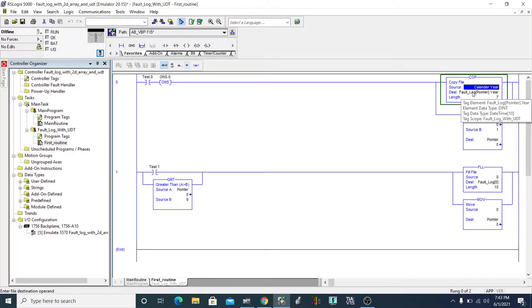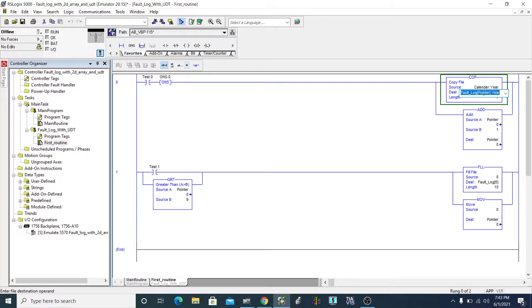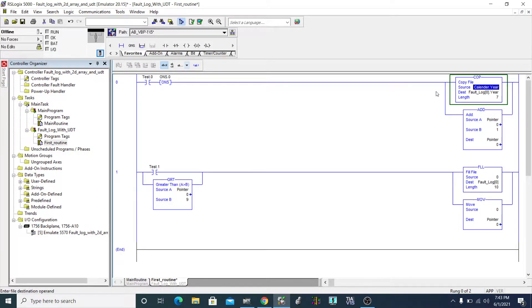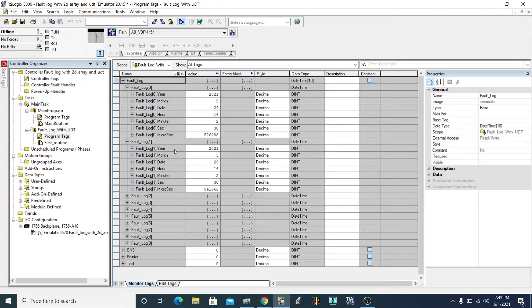I'm moving those seven elements to my fault log, but which position? Right now, instead of using a pointer, if I put just zero here — say zero and seven — then every single time I execute this rung, it will just go to fault log zero, only zero, every single time.